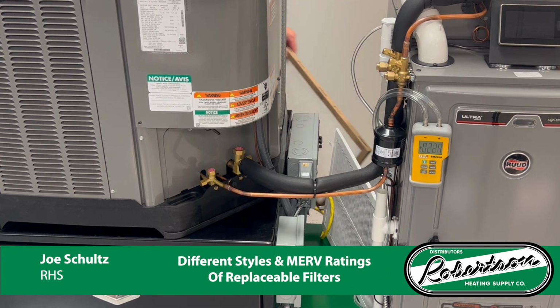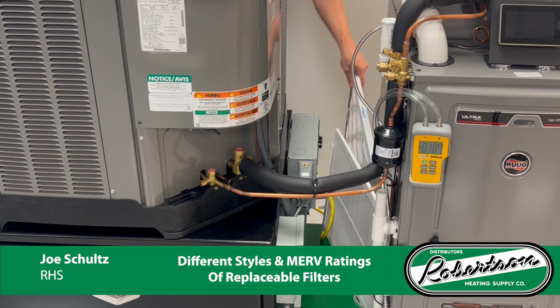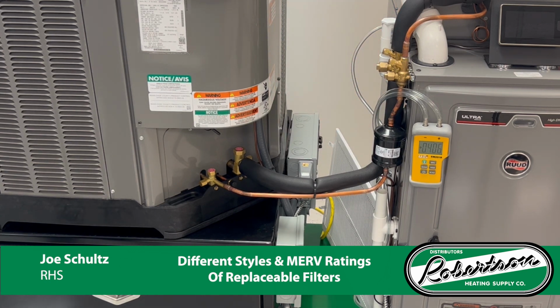So let's go to a little bit higher Merv rated filter. This is a Merv 7 filter. So you can see our static pressure has climbed, and we're almost to 0.3 inches of water, 0.39 inches of water column for our total ESP.